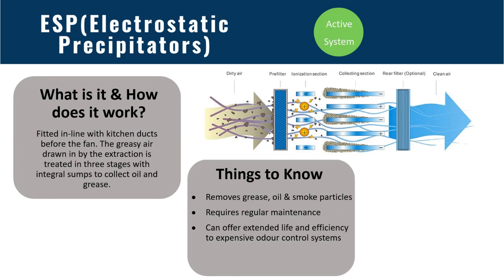ESP, which stands for electrostatic precipitators. These systems are popular with contractors and local authorities because of the reduction in nuisance that they present. They can also offer extended life and efficiency to expensive odour control systems such as activated carbon and UV ozone. They're designed to be fitted in line with kitchen ductwork before the fan.